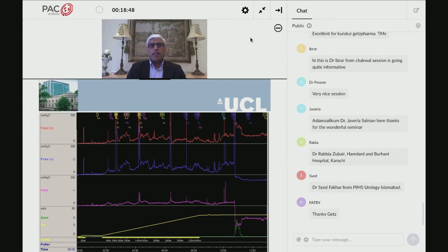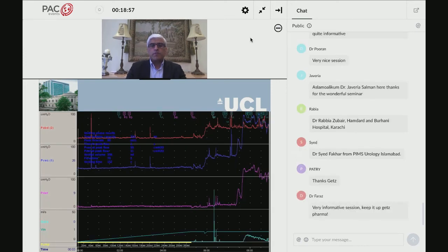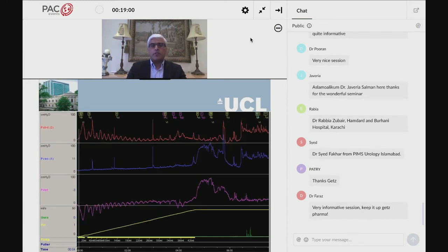This is what I said: one must not rely on computers. If you look here, because of the artifact, probably the flow meter was being adjusted so that one can capture the flow, and this is an artifactual rise. Generally, when it goes up steeply, it's an artifactual rise. If one relies on the computer, this is what you're going to get. The peak flow is 80 mils per second.